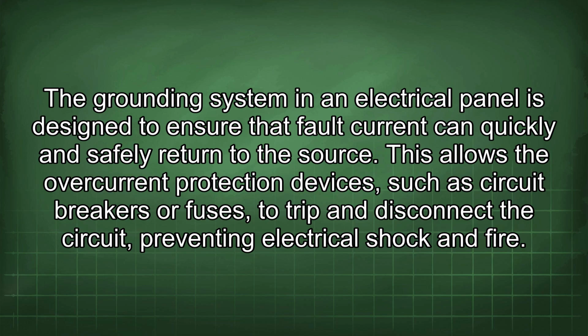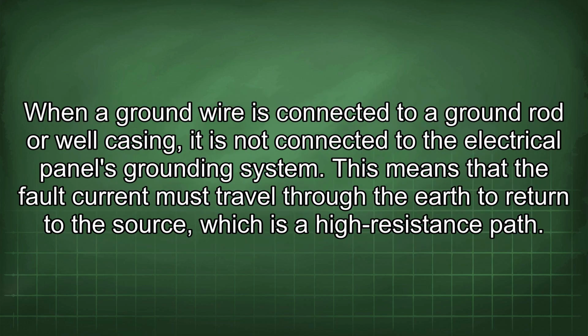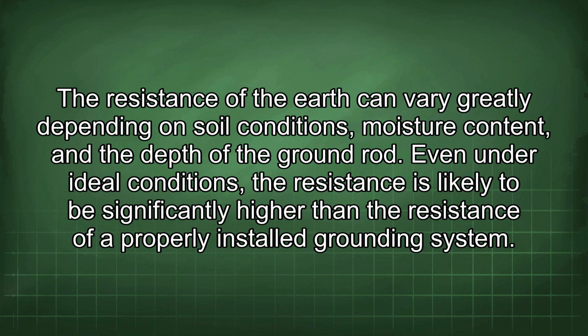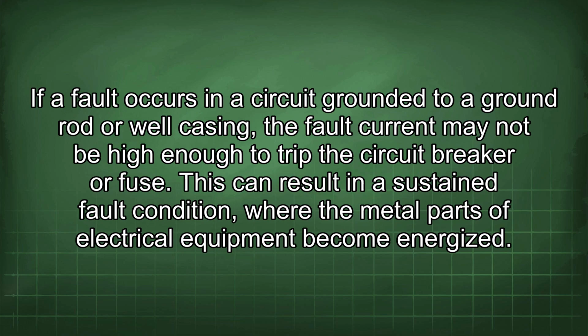This allows the overcurrent protection devices, such as circuit breakers or fuses, to trip and disconnect the circuit, preventing electrical shock and fire. When a ground wire is connected to a ground rod or well casing, it is not connected to the electrical panel's grounding system. This means that the fault current must travel through the earth to return to the source, which is a high resistance path. The resistance of the earth can vary greatly depending on soil conditions, moisture content, and the depth of the ground rod. Even under ideal conditions, the resistance is likely to be significantly higher than the resistance of a properly installed grounding system.